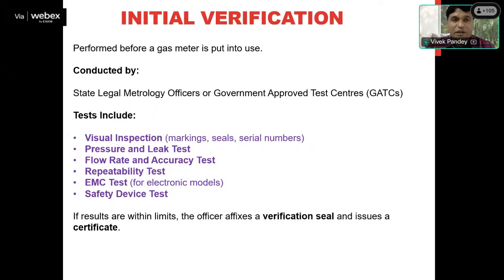Then when we talk about the initial verification: before the gas meter is put into use, model approval is done, but before it is used for transaction purposes, it must be tested again. This is called initial verification, and these tests are basically performed by the state legal metrology officers or government approved test centers. Normally these tests include visual inspection, that means the marking, seal, and serial numbers must be checked. Then it should be checked for a pressure or leak test. We should check whether there are any leakages or whether it can sustain the specified pressure of the gas.